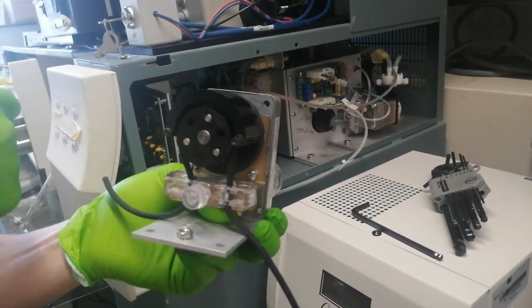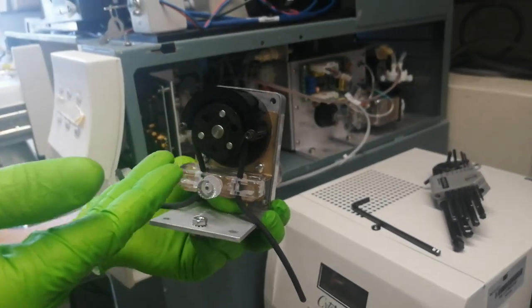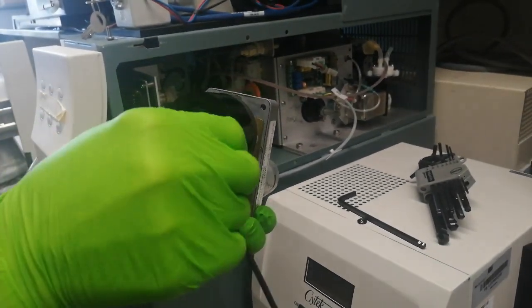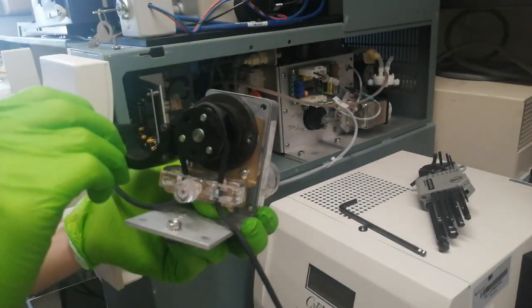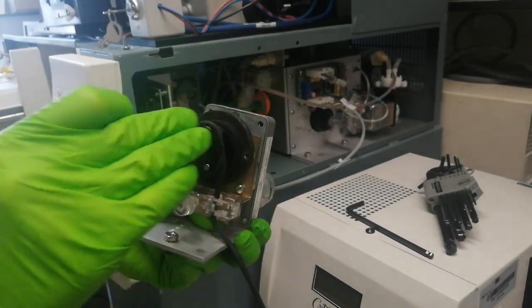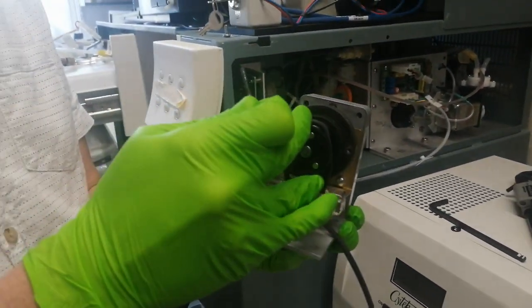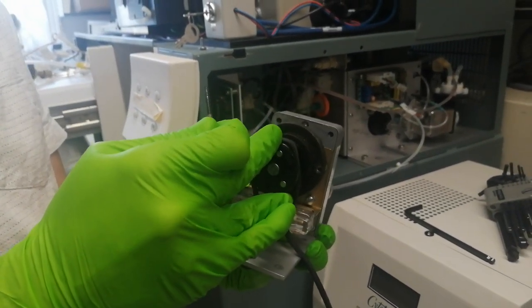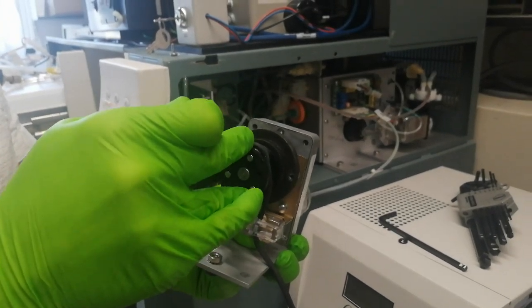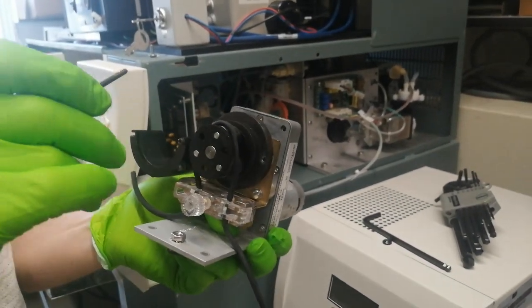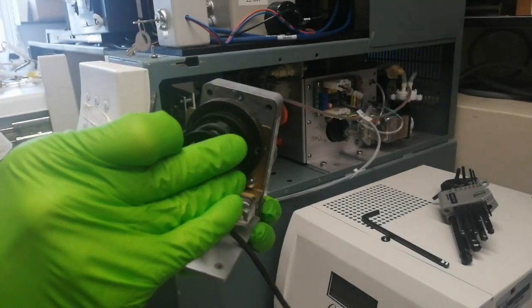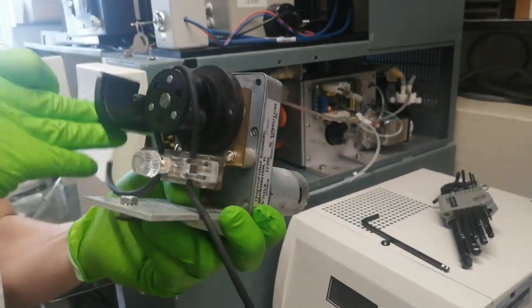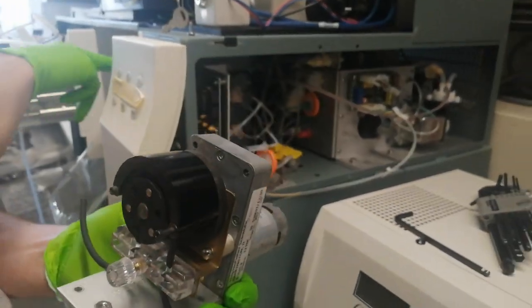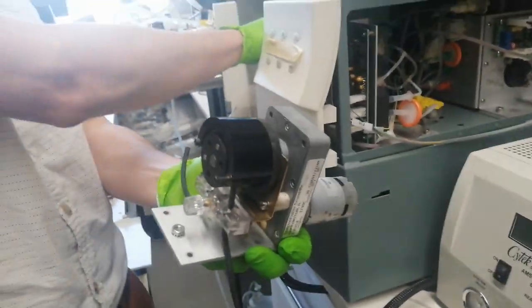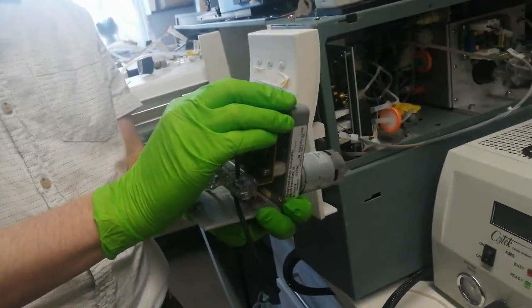If after you've done that you find that sometimes when you close the sample arm, the sample is being aspirated really quickly, it can be because there's either a problem with the way that this tubing has been seated, or more commonly it can be because this pump head has worn out, and they can become wobbly if they wear out, and then it will need replacing, the pump head. What you can do, if you use it without the outer tube, then this pump doesn't get used at all.